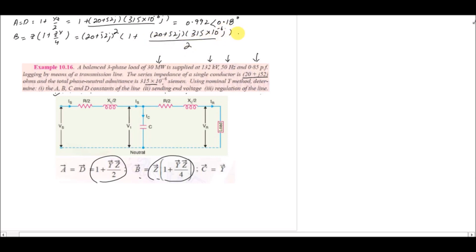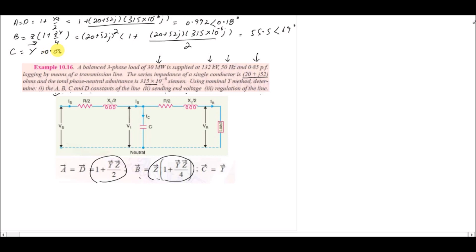For B, the value equals Z·(1 + YZ/4) using Z equals 20 + 52j and Y equals 315×10⁻⁶. After solving, B equals 55.5 at angle 69 degrees. For C, it equals the admittance value given: 0.000315 at angle 90 degrees. The units are: A and D are dimensionless, B is in ohms, and C is in siemens.